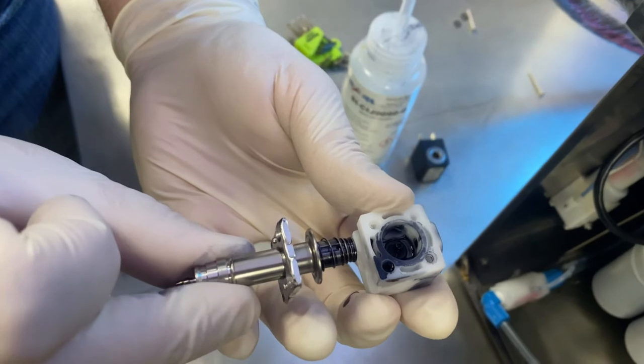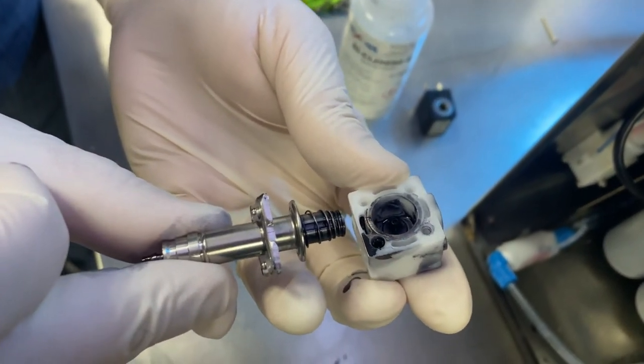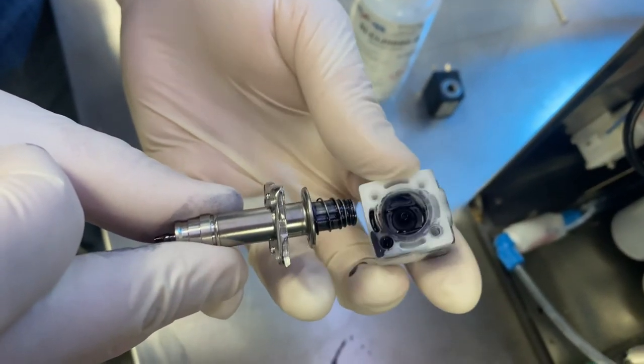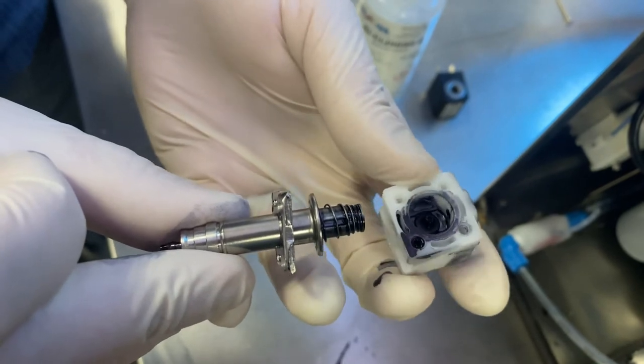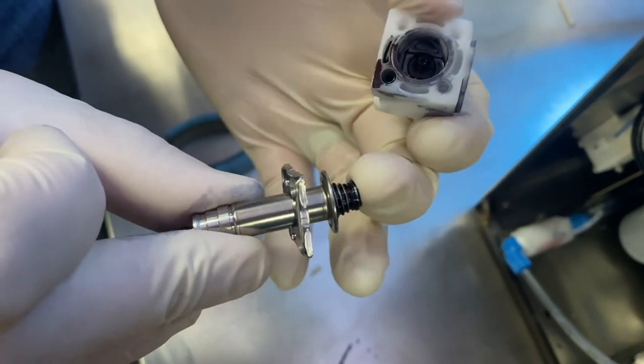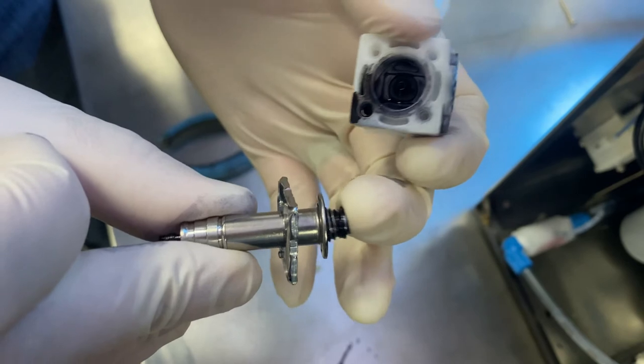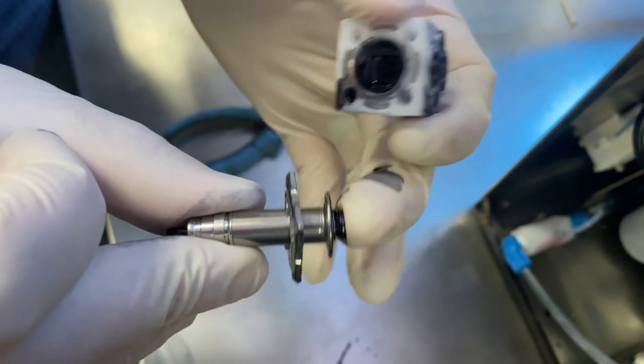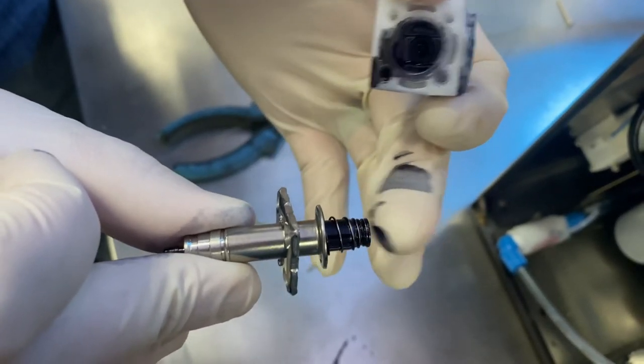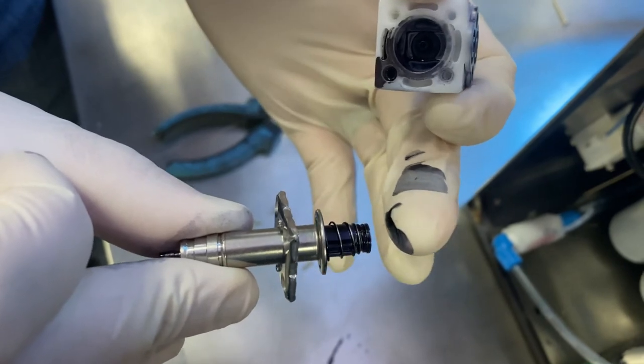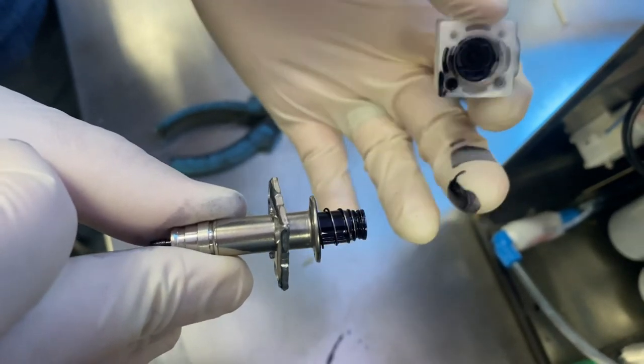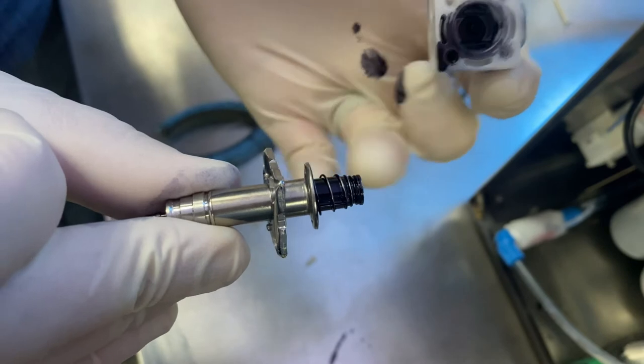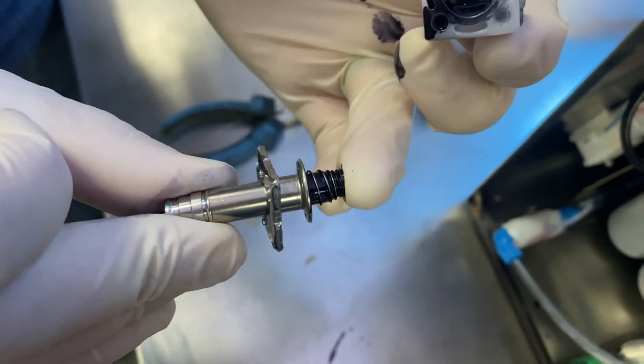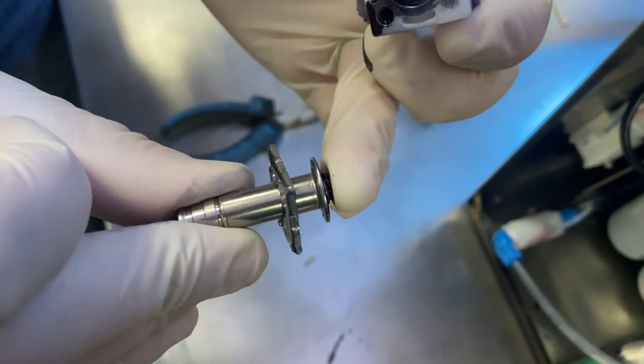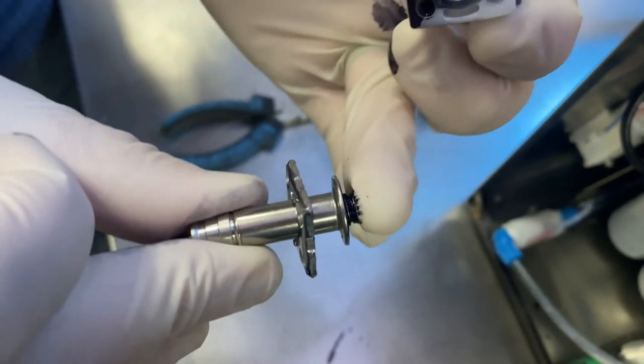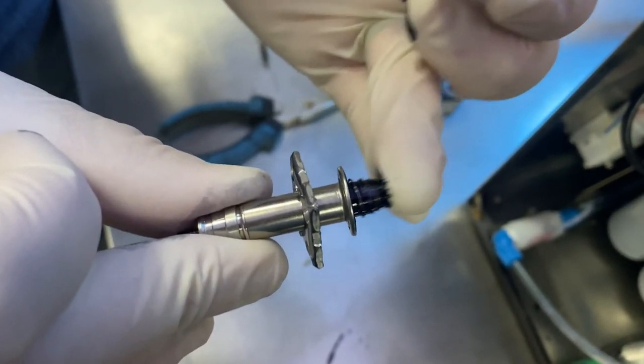Okay, so we've got our four screws out, and you'll notice there's a little bit of ink in here - a bit of a mess, not too bad. But what we're really trying to get at is this plunger right here. You'll see that's spring-loaded - this is what's opening and closing when we energize or de-energize that solenoid. If the valve wasn't functioning, this is typically stuck, usually stuck in like this. So if this is moving freely, that's a great sign.